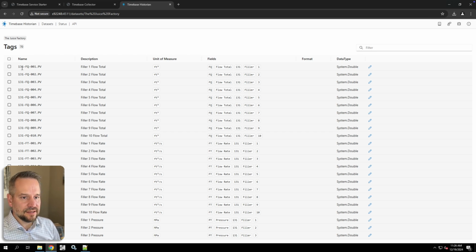So here's my tag name, 131fq001.pv. What does that mean to me? Well, I do have a description, and my description is that that is associated with filler 1, and it is a flow total. Notice that I have a unit of measure, cubic feet, and I have some fields. An FQ field, a flow total field, a 131, a filler, and a 1 field. So this represents different pieces of metadata about this tag.